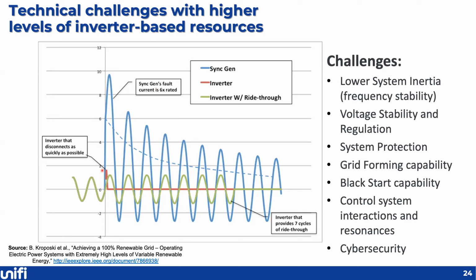Inverters, on the other hand, don't typically have that capability, and so you can get a variety of outputs when you fault an inverter. They can react very quickly, as in this red line here, where they detect the fault condition and disconnect in a quarter cycle down to 0. Or the inverter could ride through for several cycles, as in this case, and then trip off. But in either case, neither of these lines looks like the large amount of fault current provided by synchronous generators. So new protection schemes really need to be designed around how we incorporate inverters and recognize fault problems on the grid.